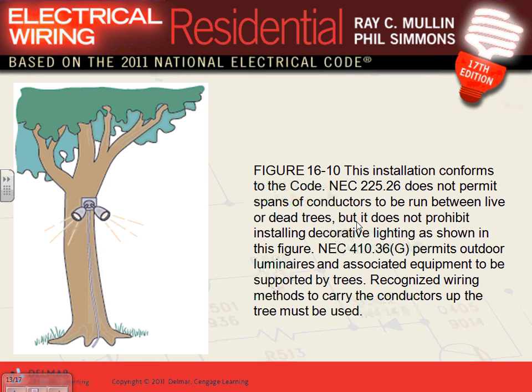Is this code? Can I mount a fixture to a tree, to vegetation? Yes. Mounting a fixture to vegetation, yes. Using the vegetation as your poles to support the power lines, no. Does that make sense? This installation conforms to the code: it does not permit spans of conductor, but it does not prohibit installing decorative lights as shown. So if you have a decorative light, you attach it to a tree, that's okay.